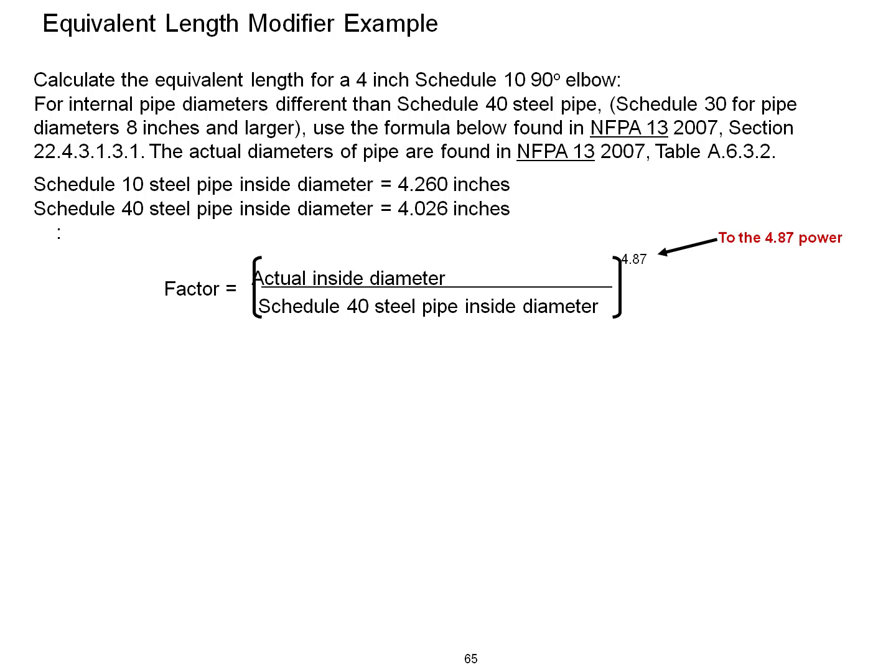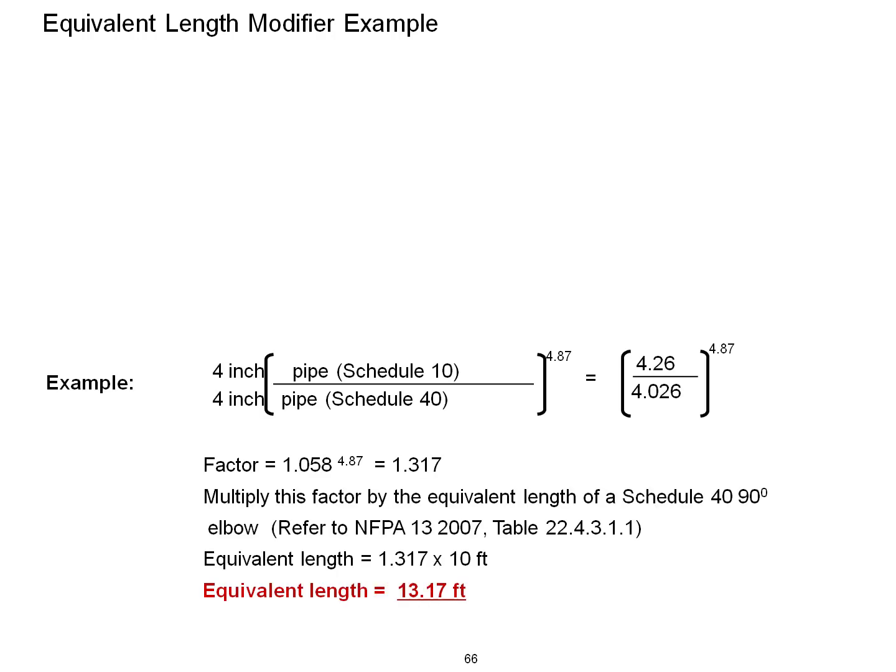The actual diameters of pipe are found in Table A.6.3.2. Continuing our example, for 4 inch pipe, Schedule 10 is divided by 4 inch pipe Schedule 40 to the 4.87 power. Therefore, we have 4.26 for Schedule 10 and 4.026 inches for Schedule 40. We divide 4.26 by 4.026 to the 4.87 power. 1.058 to the 4.87 power equals a factor of 1.317. Multiply this factor by the equivalent length of a Schedule 40 90 degree elbow.